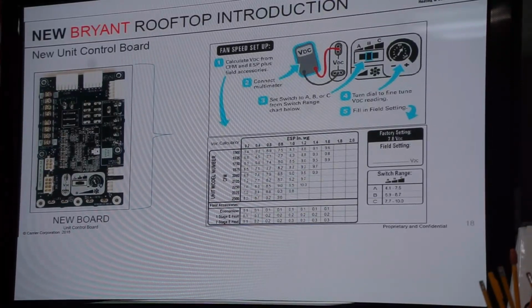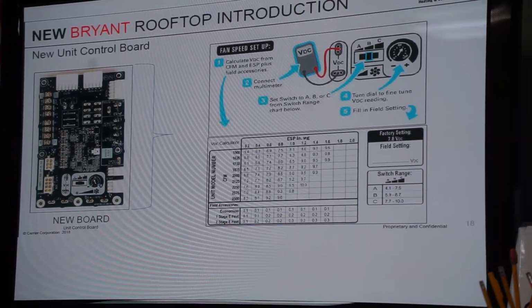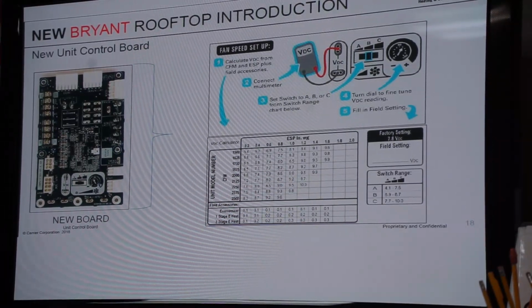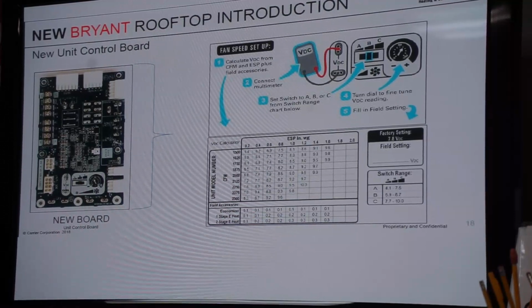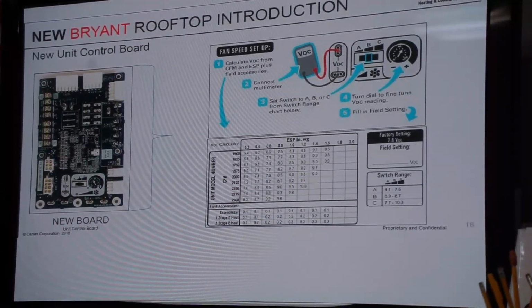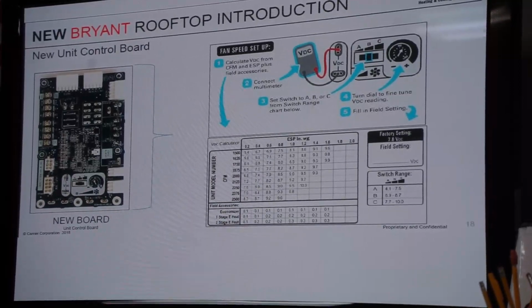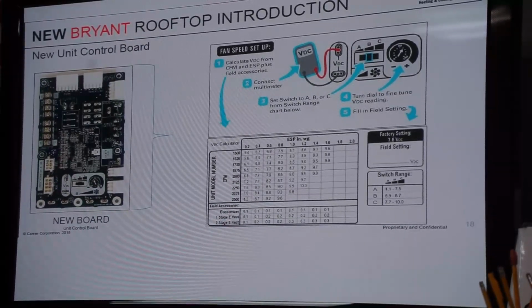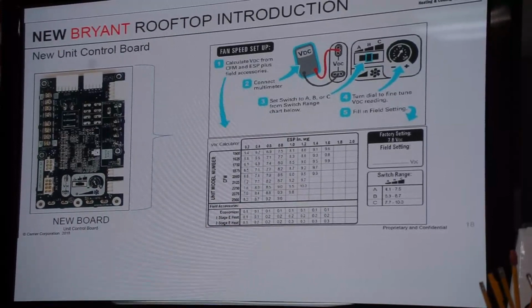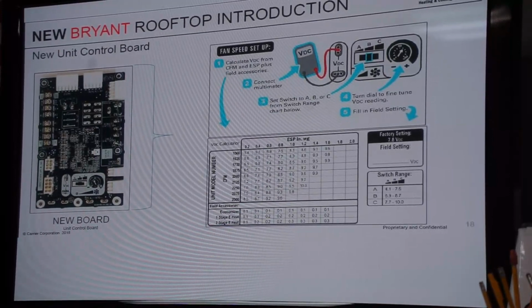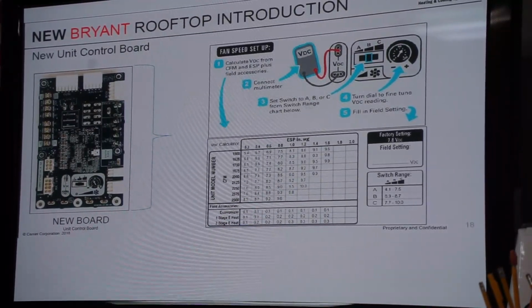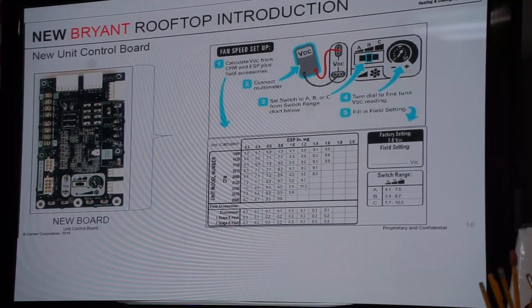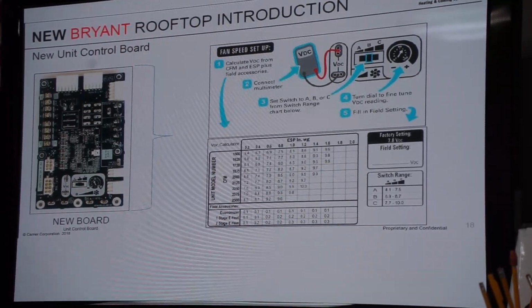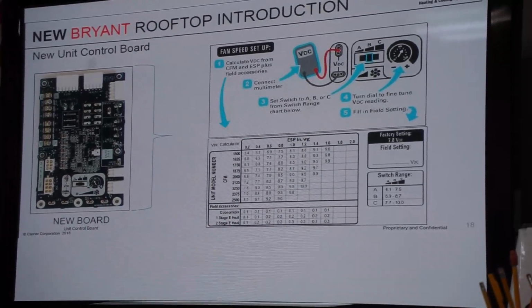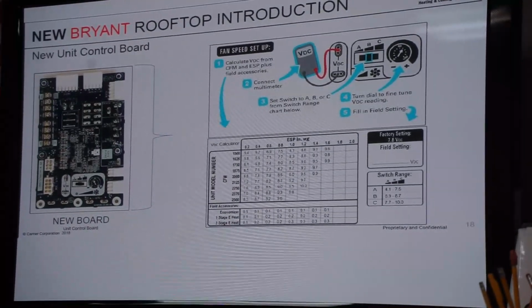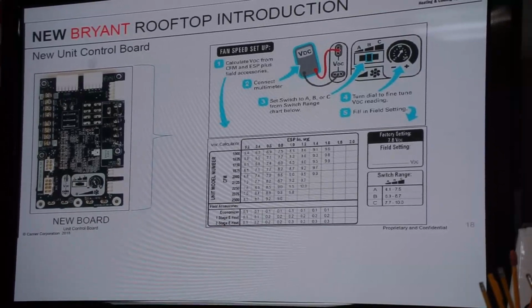I can now check my temperature rise, my drops, what kind of suction pressure do I see, commission that unit. And if I've got to tweak it one way or the other, it's obvious it's moving way too much air. You know, it's howling into space. Pulling my screwdriver out and I'm slowing it down that way, versus taking the motor, sliding it forward, rolling the belt off, taking the Allen wrench out, unloosening the sheave or the set screw on the sheave, rolling it in or out. I'm doing that all with the screwdriver. Life is good.